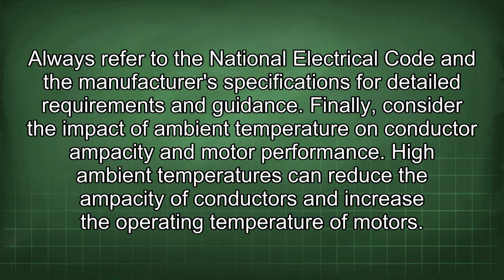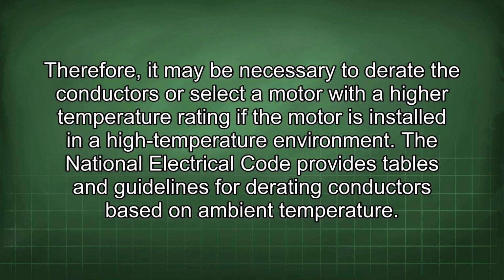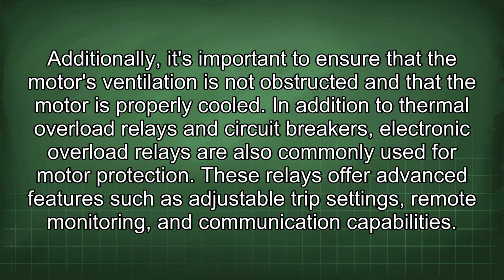Finally, consider the impact of ambient temperature on conductor ampacity and motor performance. High ambient temperatures can reduce the ampacity of conductors and increase the operating temperature of motors. Therefore, it may be necessary to derate the conductors or select a motor with a higher temperature rating if the motor is installed in a high-temperature environment. The National Electrical Code provides tables and guidelines for derating conductors based on ambient temperature. Additionally, it's important to ensure that the motor's ventilation is not obstructed and that the motor is properly cooled.